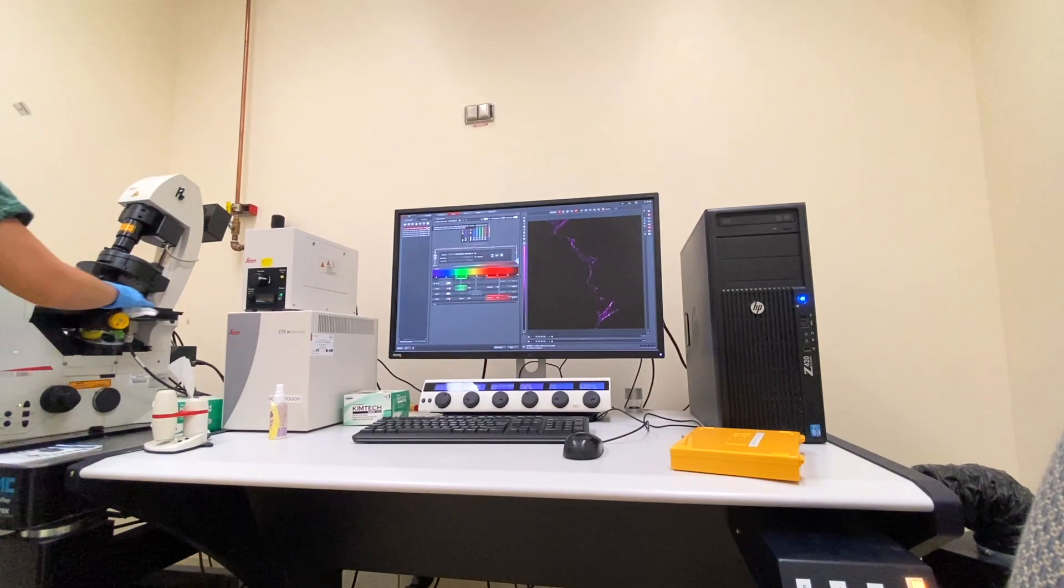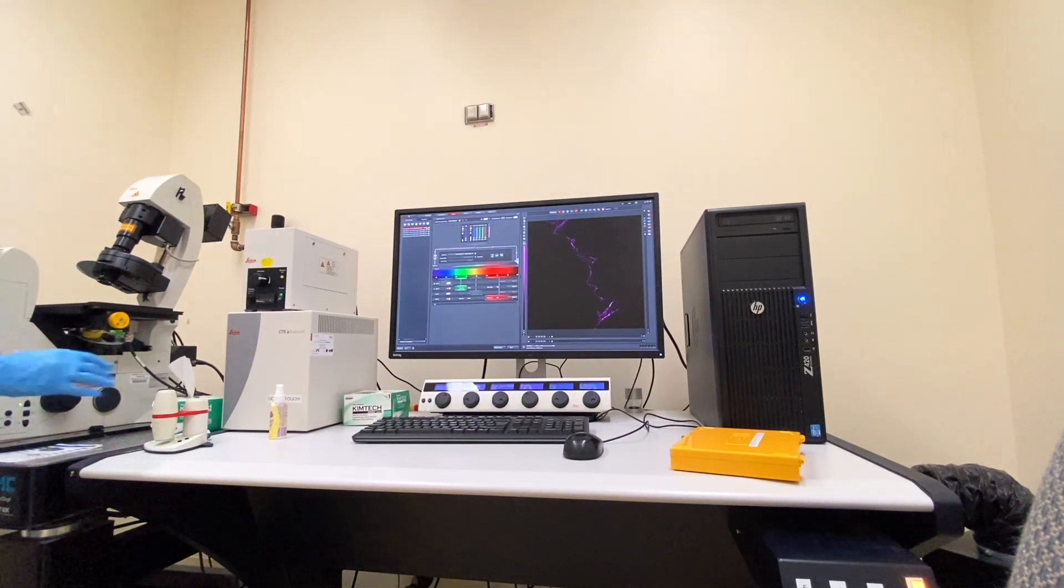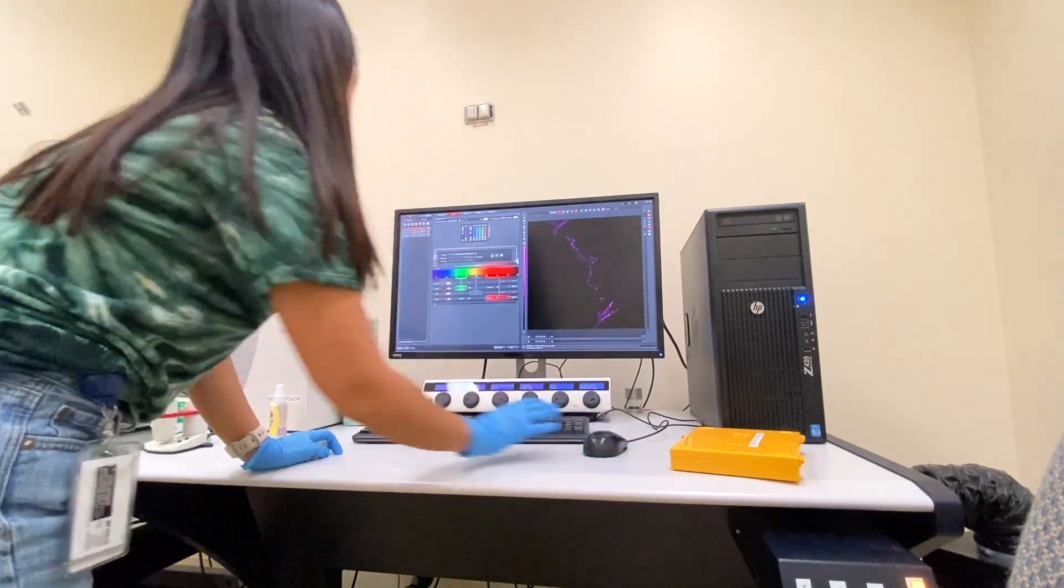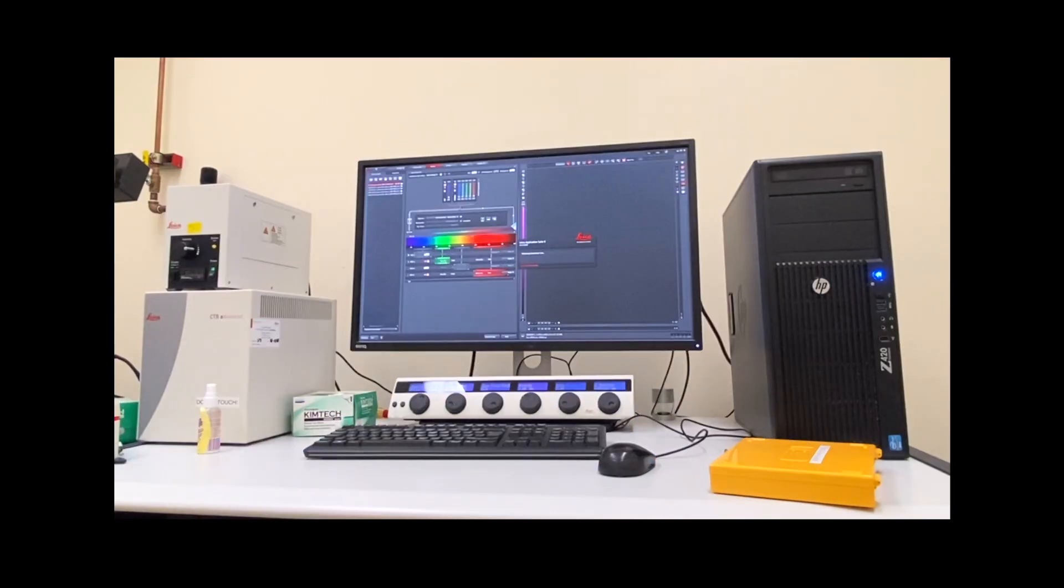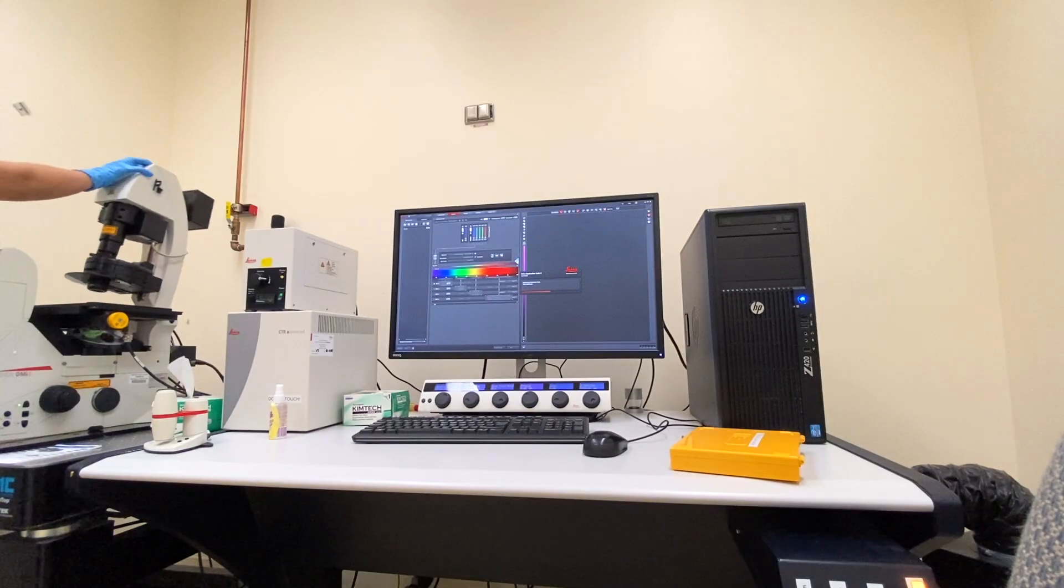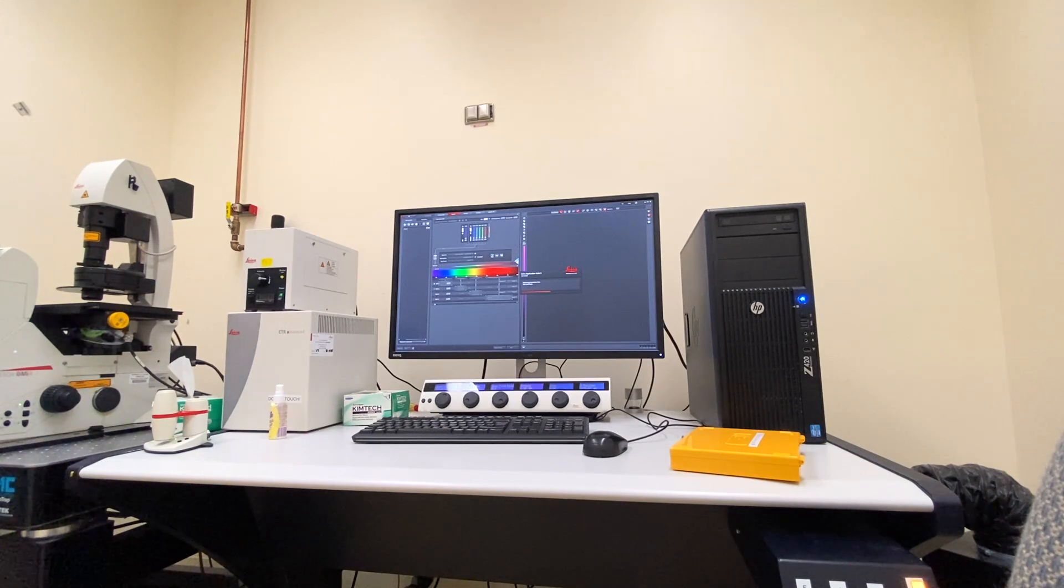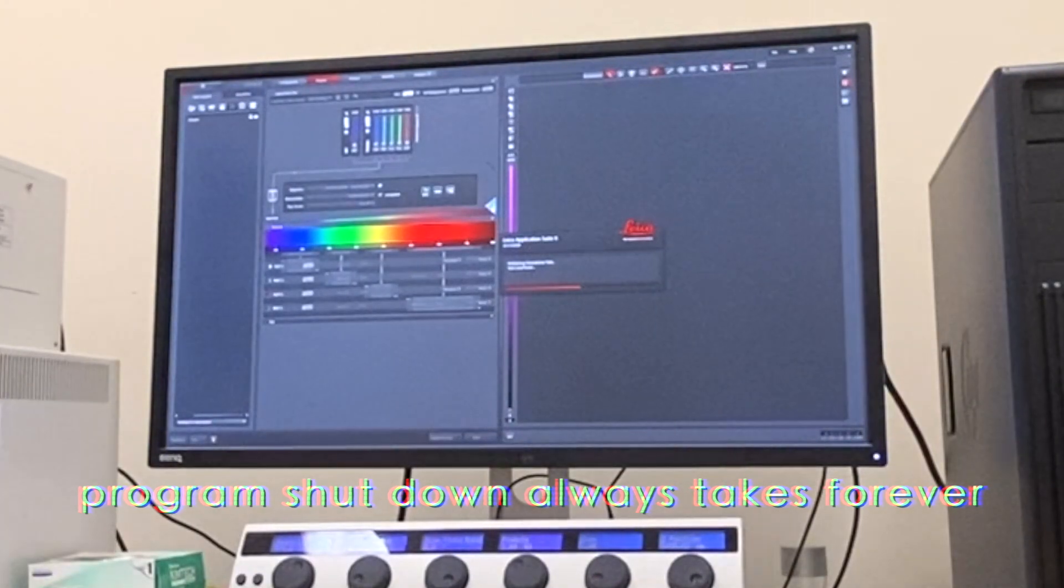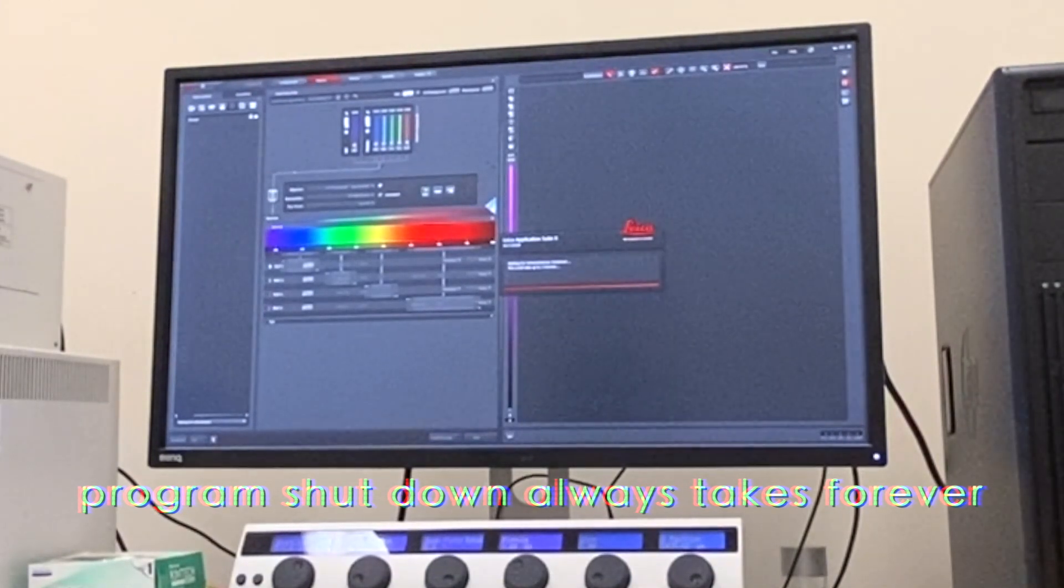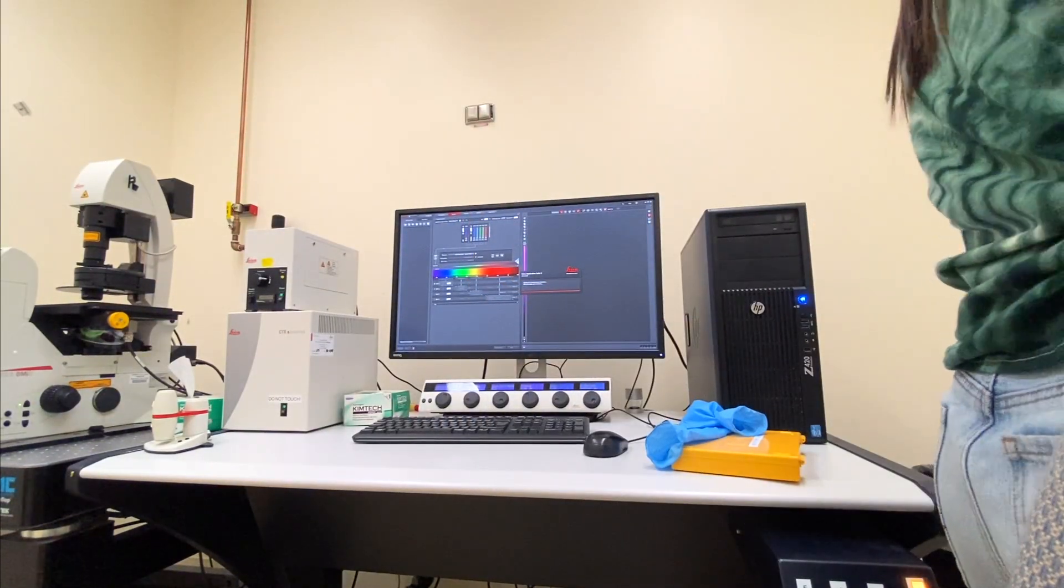I shut down the program after everything saved. And then I log out, shut down the computer. And typically at this point, you would check on a shared calendar schedule if someone is going to come in after you or in the near future if it's a normal work day. But since no one is coming after me since it's the weekend, then I can turn off the microscope completely and shut it all down so that it's not running overnight. And there's a specific order to do this so the laser can cool.